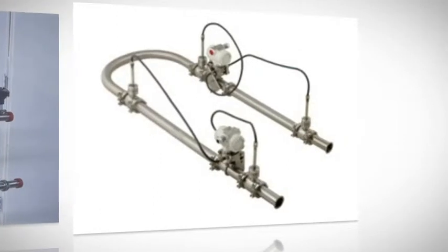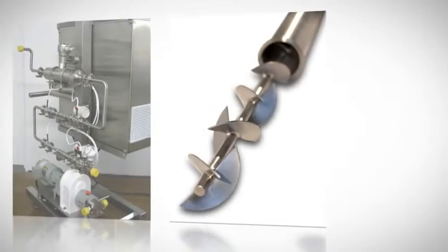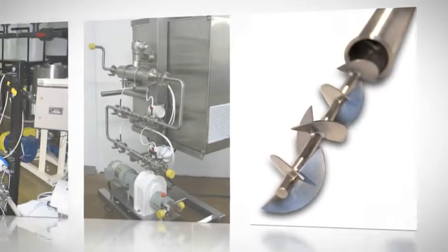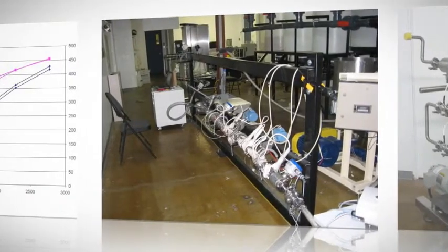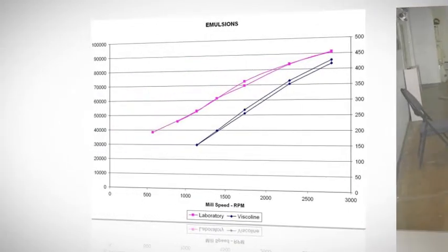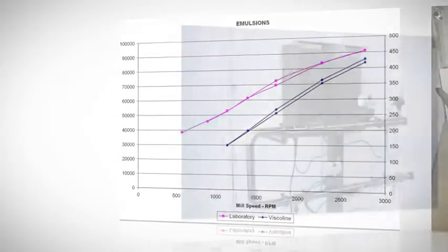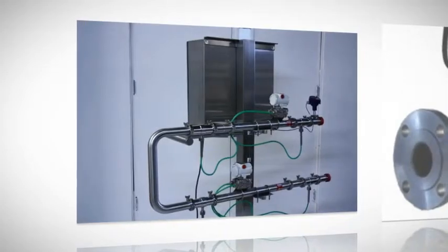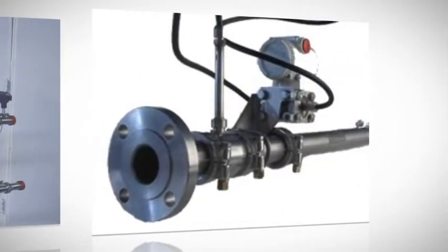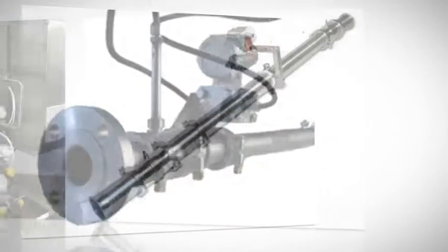Since direct measurement is challenging, quality control technicians frequently have to infer viscosity from other measurements or devise complicated control strategies to minimize variations. Lab-analyzed samples, periodically drawn from production batches, do provide some measure of feedback for process control or quality control when real-time information is not available. Today, quality-conscious customers are definitely seeking ways to control viscosity more tightly to optimize resources or eliminate off-spec product.